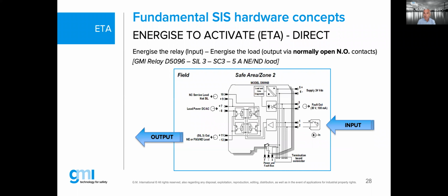I got two examples by memory because I do not know the slides coming up. I don't have any preview, but I think we have two slides. One is this one. What is sometimes confusing, and I have seen it myself many times in configuration, sometimes people will use de-energized to activate, de-energized to trip examples or loops, enabled to energize to activate loops in the field. That means they kind of start to reverse engineering. That is why I start here with a direct engineering, and I call this direct engineering.